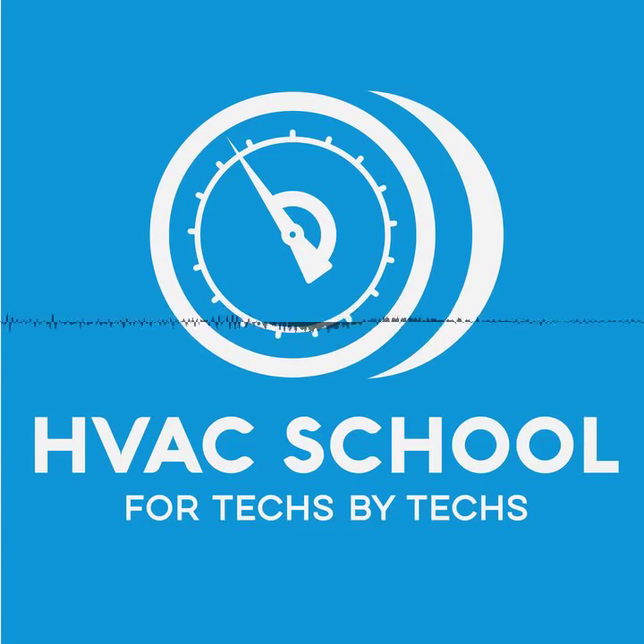yellow and blue. In a straight cool, in a lot of cases, you're just energizing the contactor. But on a simple heat pump, you've got red, yellow, blue, white, and orange, okay? So you've got multiple conductors there, and they all do different things. They serve different purposes. And then you also have common. I don't know if I said blue already, but you also have common.